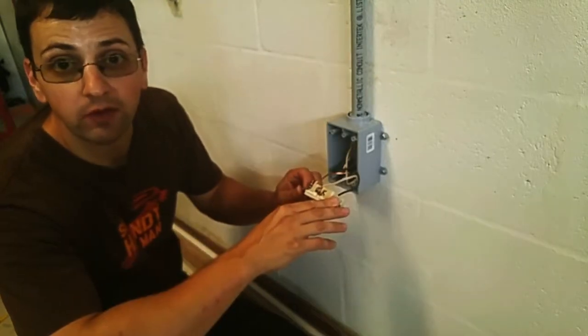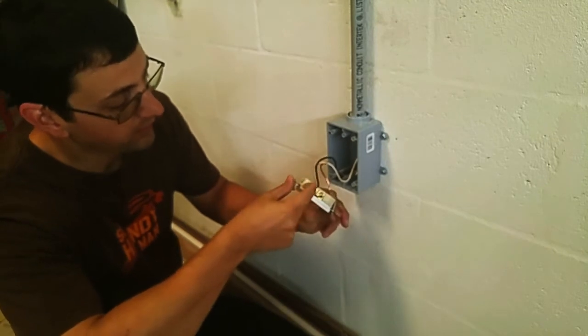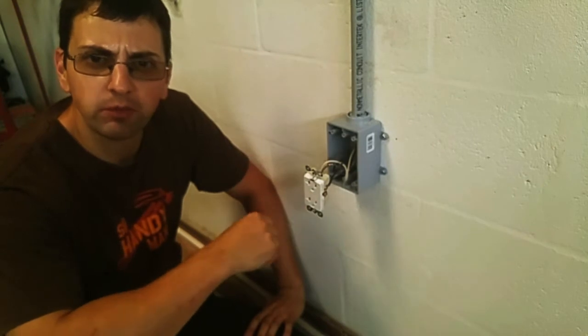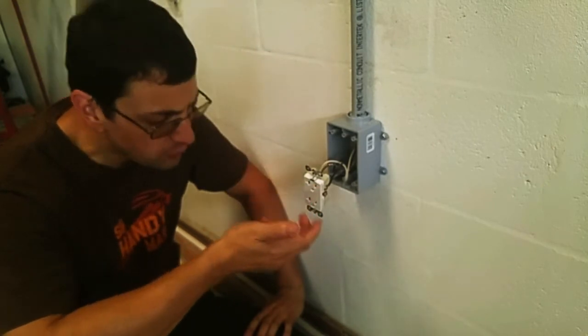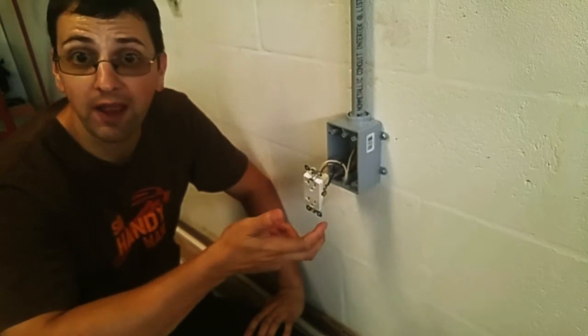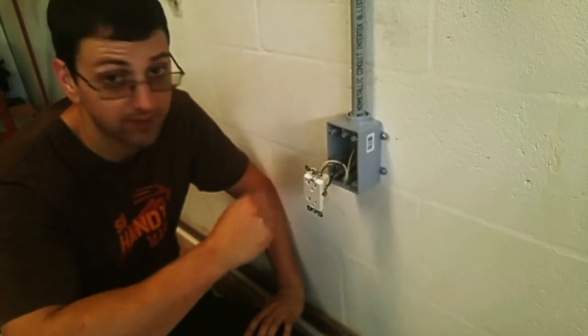The reason I mention that is you'll notice the neutral is on the bottom screw, the hot is on the top screw. There's actually a reason for that. You see, if they were both on the bottom screw, the wire would be directly connected to the bottom terminal. Voltage would have to pass through that thin tab on both sides to get to the top outlet.